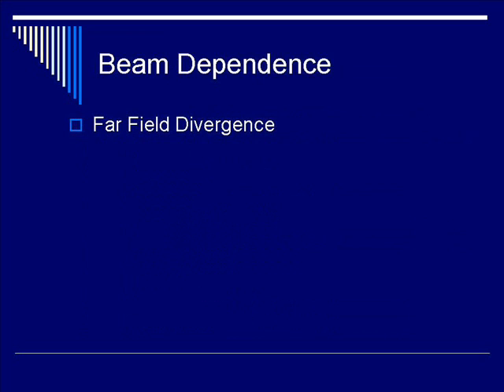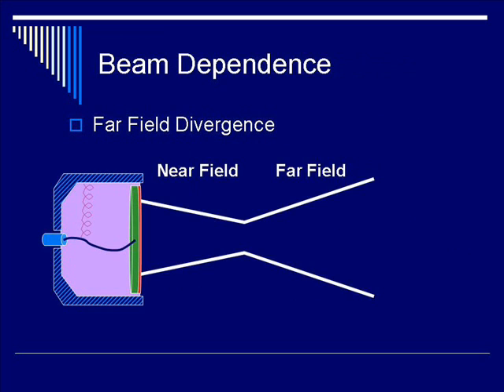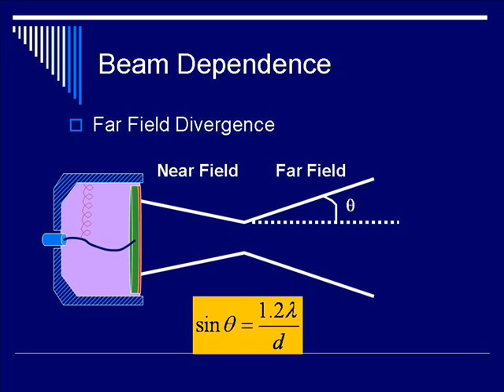Let's talk about far field divergence. This is the angle between the boundary of the ultrasound beam relative to the horizontal line, as defined in the diagram. Theta is the angle of spread of the ultrasound beam beyond the minimum beam width. Sine theta, by this definition, equals 1.2 lambda divided by D. Note the equation applies to an unfocused single transducer element.